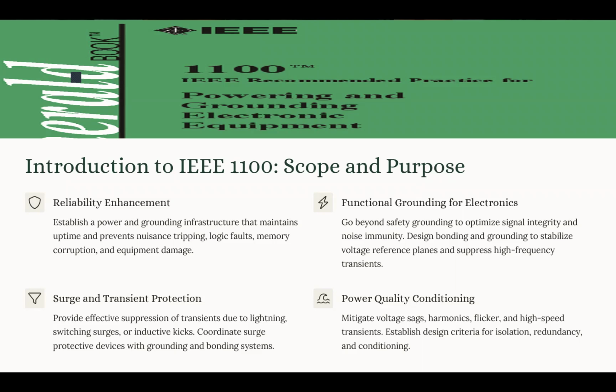Now we have the noise immunity function, which is suppressing high frequency transients that can couple into the data lines. We also have voltage reference stability as a function of functional grounding, where bonding and grounding are designed to maintain a consistent reference plane for all the interconnected devices.